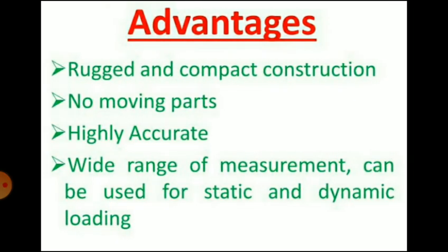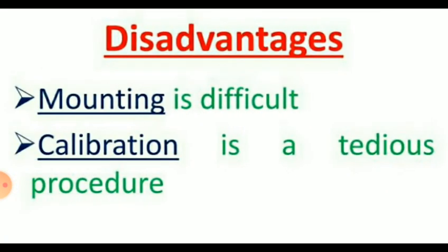Then the advantages of load cells: it has rugged and compact construction, it has no moving parts, it is highly accurate, it has a wide range of measurement, and it can be used for static and dynamic loading. Disadvantages: the mounting is difficult and calibration is a tedious procedure.